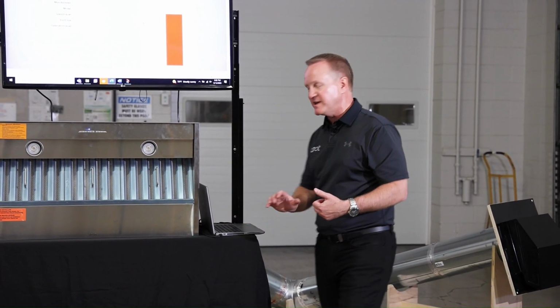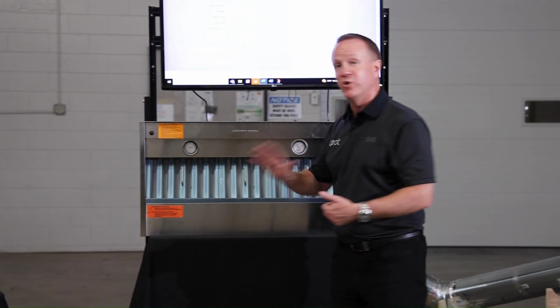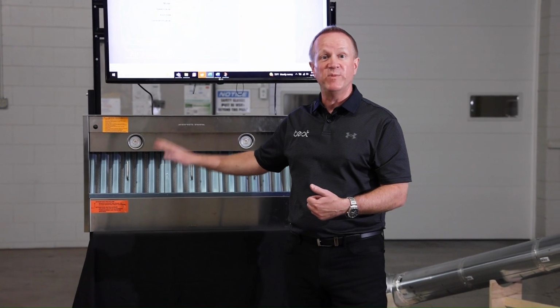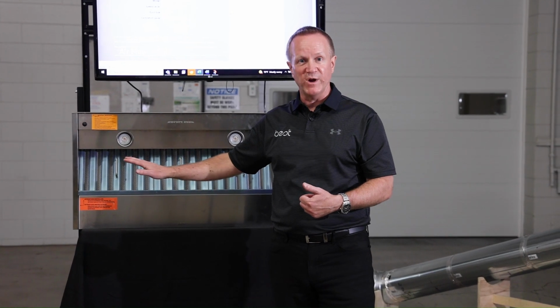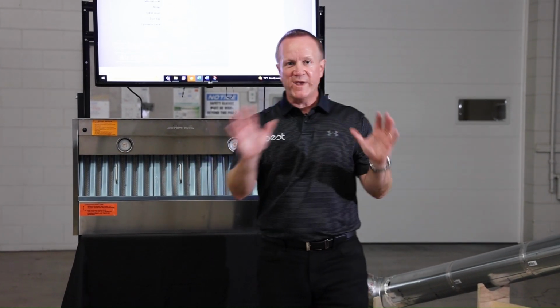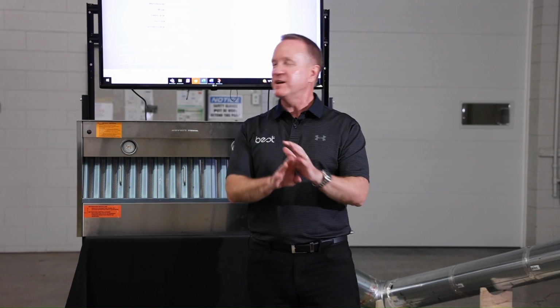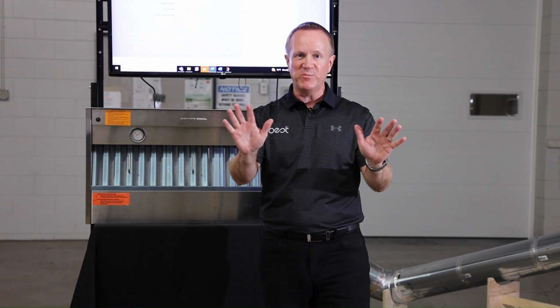So I'm actually going to stop our test and turn our hood off, because our hood does have to be off in order to do calibration. So in order to do calibration, it sounds very technical. It doesn't require any tools other than a thumb, any finger, any digit basically.